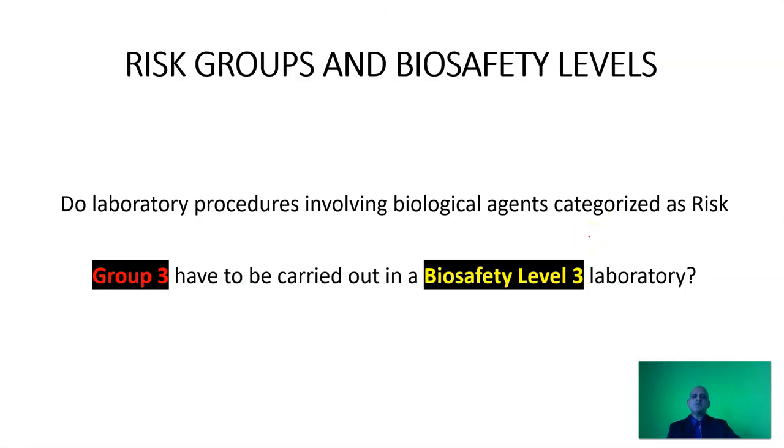One of the questions which has been posed by many biorisk managers and biosafety officers is: do I need to work in a BSL-3 facility when my pathogen has been categorized as risk group 3? The answer is it depends on your administrative controls. You can work with a risk group 3 pathogen in a BSL-2 laboratory. However, you must implement the appropriate administrative controls in terms of standard operating procedures. This must be done on a case-by-case basis after a thorough risk assessment.